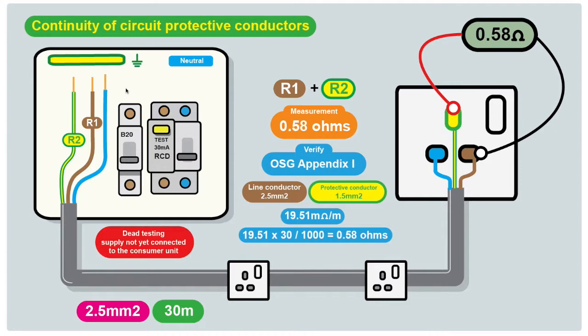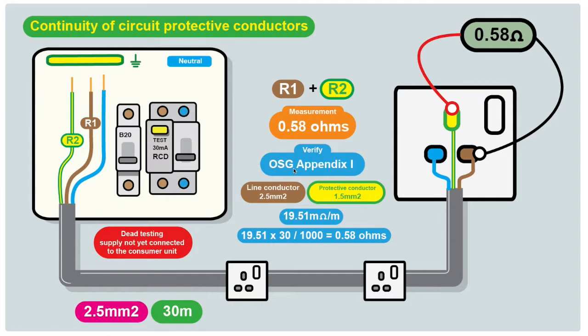Now we want to work out if this reading of 0.58 ohms is acceptable. What do we know about this circuit? We know it's wired in 2.5 millimeter squared twin earth cable. We know the cable length from the consumer unit to the furthest point is 30 meters. This is where we can use the on-site guide to help us verify that the measured reading is within an acceptable range.